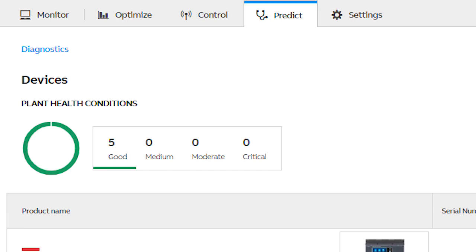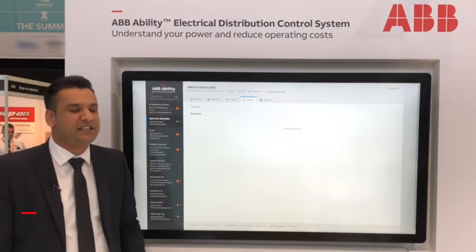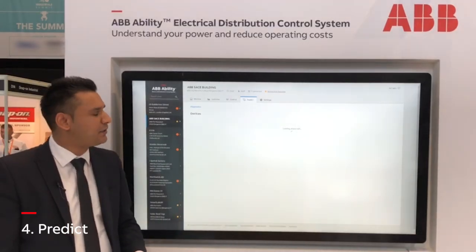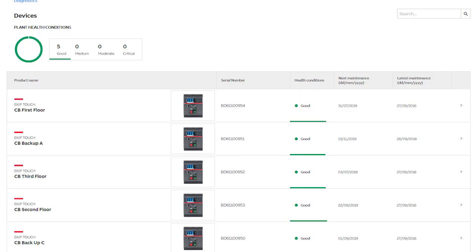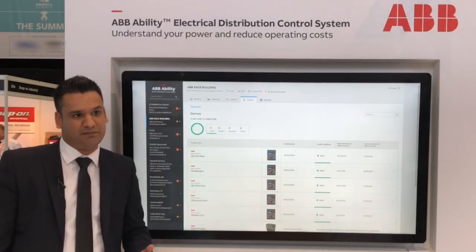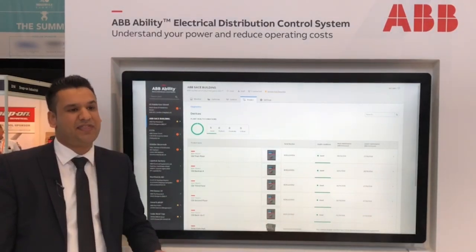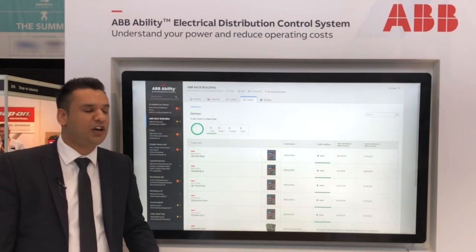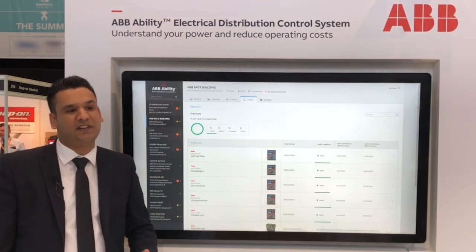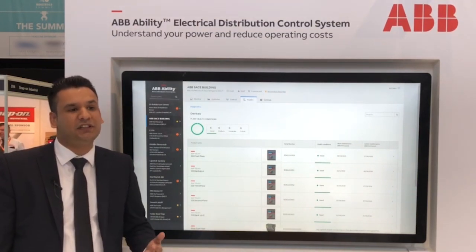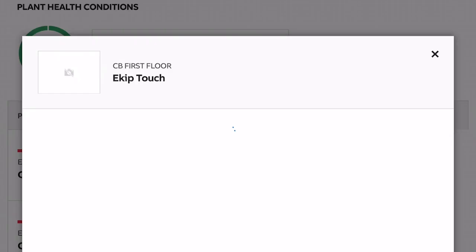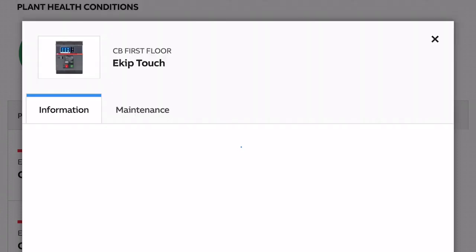The last pillar is Predict, which is for predictive maintenance on our air circuit breakers. Before this technology, we had to do preventative maintenance with annual service. Over a 25-year lifecycle, that would be 25 services. With this system, that can be reduced to almost nine services.